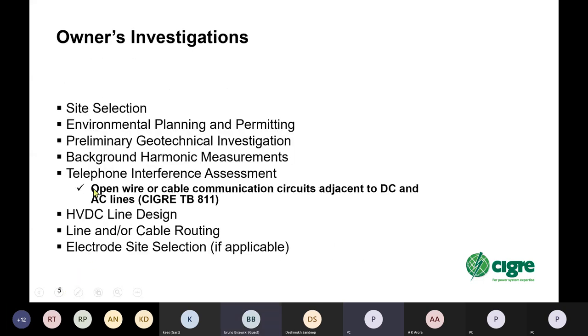Other owner's investigations include the site selection. Of course, it's good to place the site in the optimal location near the appropriate buses in the AC system and in good environmental areas so that they're safe from flooding and that kind of thing. So there's environmental planning and permitting, preliminary geotechnical investigations on the sites, background harmonic measurements, telephone interference assessments, and that's primarily to identify how many open wire or cable communication telephone circuits are adjacent to the DC and the AC lines near the converter stations.